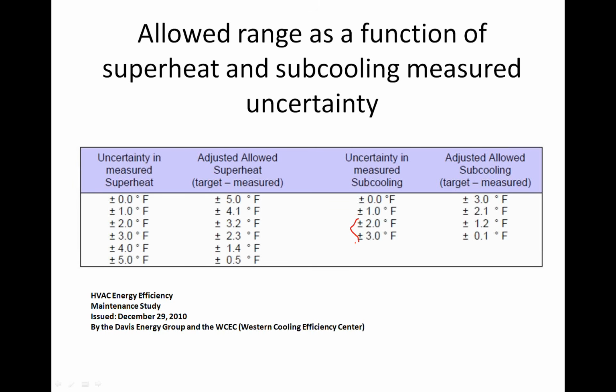Now, if we're talking a fixed orifice system, and our total uncertainty is plus or minus 5 degrees, you have to be within half a degree of the target superheat. You may be able to do it, but I doubt it. So this is where it's become critically important. We talked in one of the earlier classes about how high efficiency systems are sort of like race cars, if anybody's into racing at all. The difference between a 13-second car and a 10-second car is a lot of money, a lot of tuning and a lot of work. You just can't make a production 10-second car and have it be reliable. I mean, these are race cars.